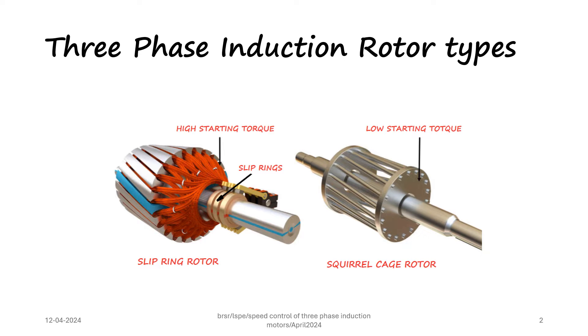There are two types of three phase induction motors, and the rotors of the two types are shown here. One is a slip ring rotor and the second one is a squirrel cage rotor. The squirrel cage rotor has copper bars or aluminium bars connected to the end ring — it is a completely closed structure. The slip ring induction motor has a three phase winding which is star connected, and the three ends of the winding are taken out and given to the slip rings. It is also called a wound rotor induction motor.